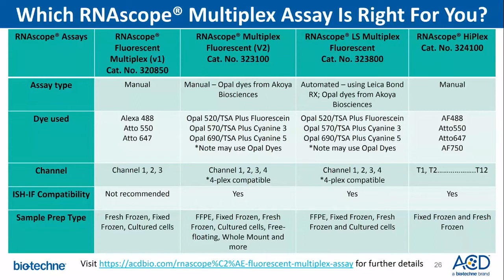So in order to do the assay, you will need pretreatment reagents, you will need the detection kit that has the amp, and then you will need the wash buffer to do the washing steps. Please note, the wash buffer is provided at 50x and would have precipitation. In order to dissolve the precipitate, we recommend that you warm the wash buffer at 40 degrees for 20 minutes, which will dissolve the precipitate.